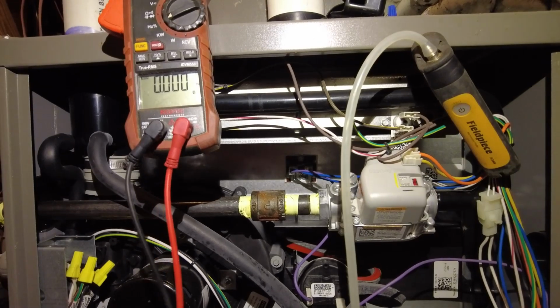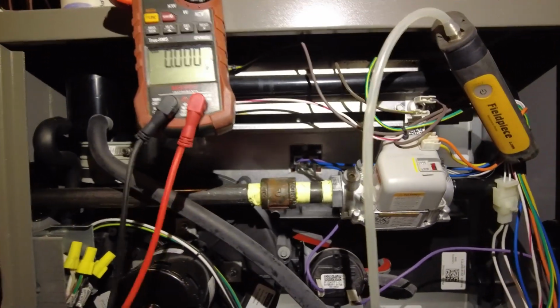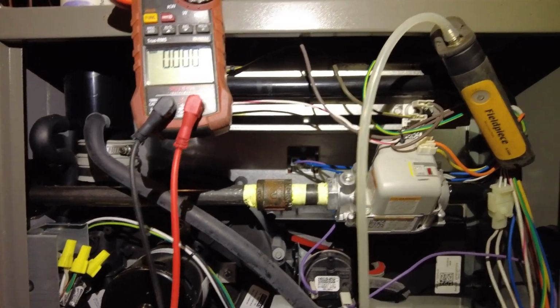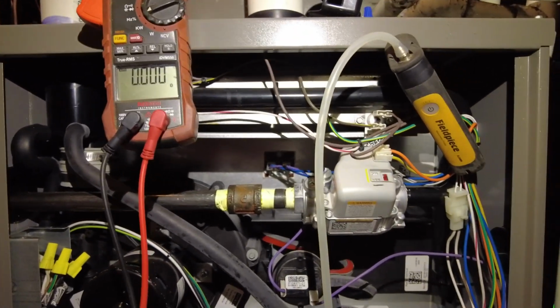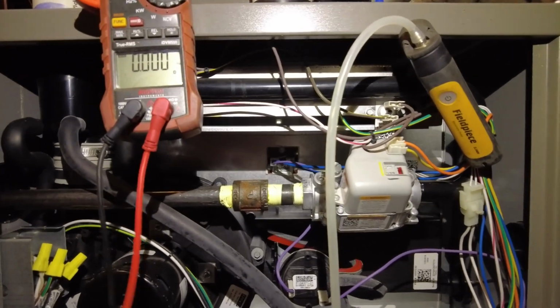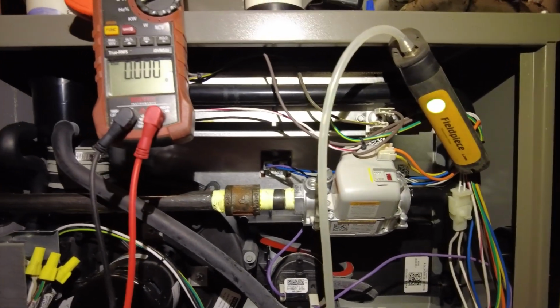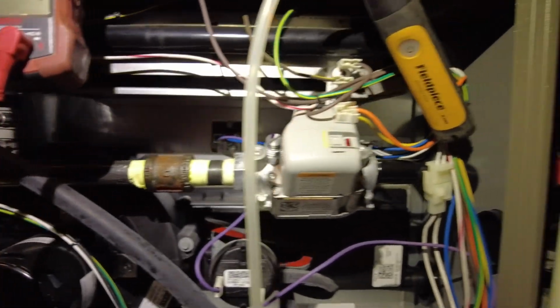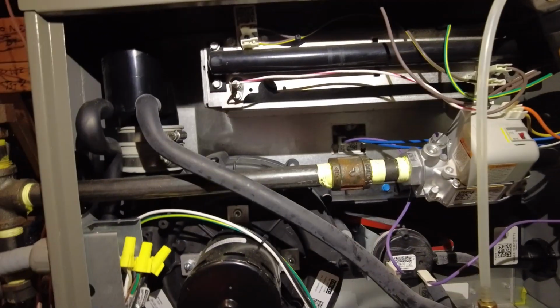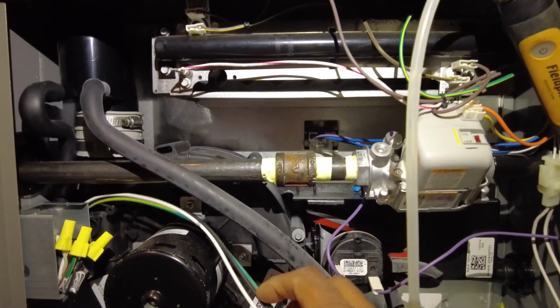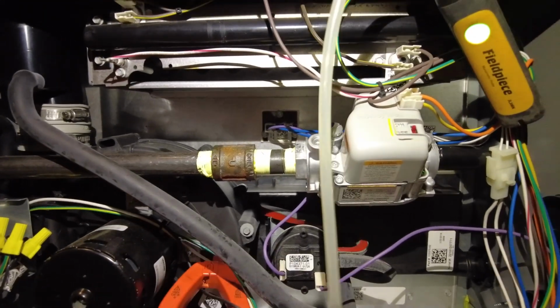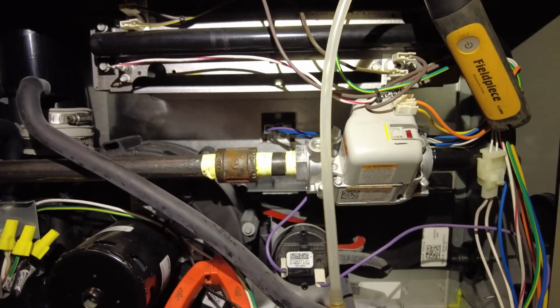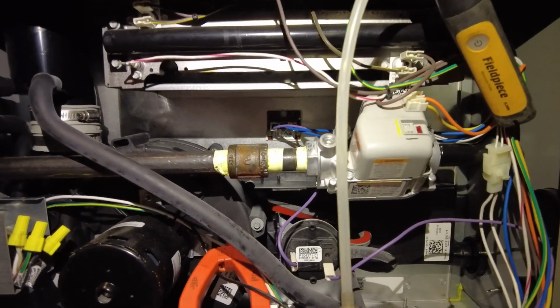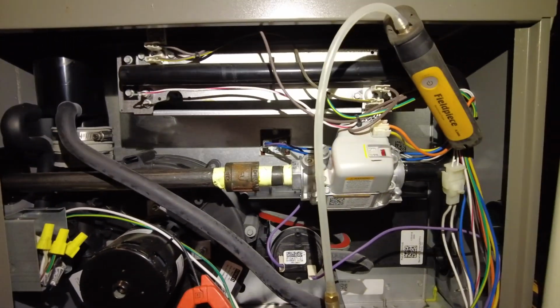Basically, shut the bypass off completely, and then let the motor slip as the static pressure increases, because a PSC motor is not necessarily trying to ramp up. It doesn't cause overheating. You will lose capacity, but the motor itself isn't being affected, and it actually costs less energy. As the static pressure increases, the PSC motor draws less current and automatically governs itself by ramping down in speed. Like I said, you're losing capacity, but it's not causing any harm to the motor as it would with an ECM motor, a variable speed motor.